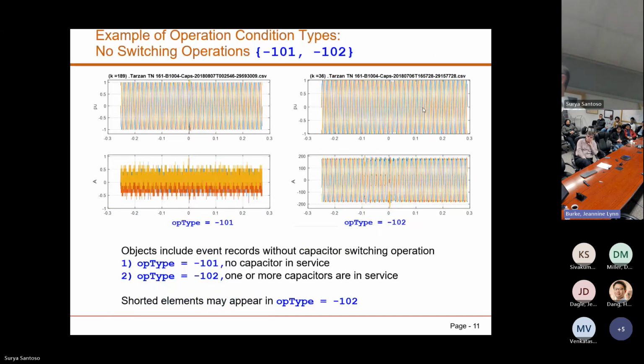So this is one operation type here - this is like no switching operations, you can see that from here. This is the voltage waveform, and this is the current waveform. This current waveform is 0. So what does it mean, this current being 0? Do you think there is any capacitor bank in operation in the substation? This is the voltage measured at the main bus, this is the current measured at the capacitor bank bus, the circuit breaker, and it's 0. It means there is no capacitor in operation, right?